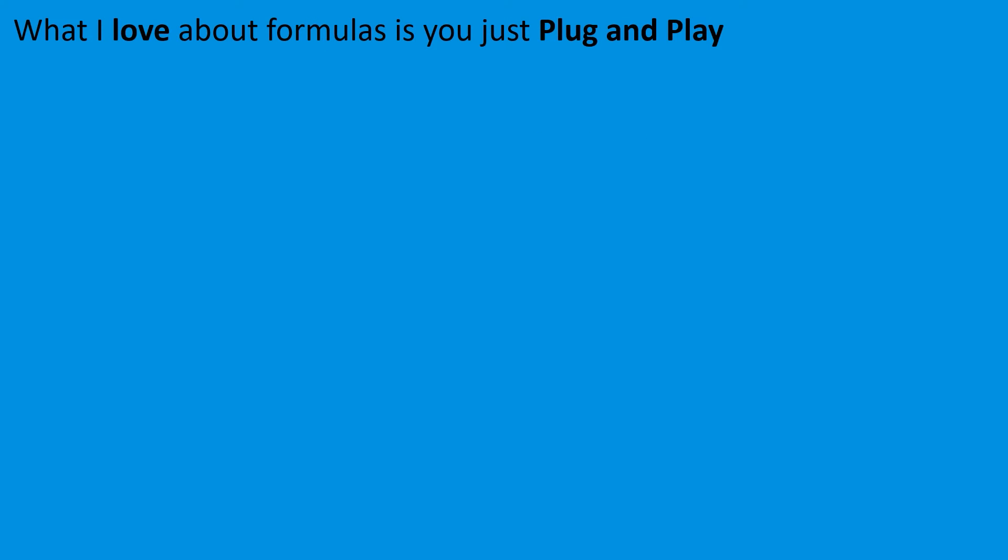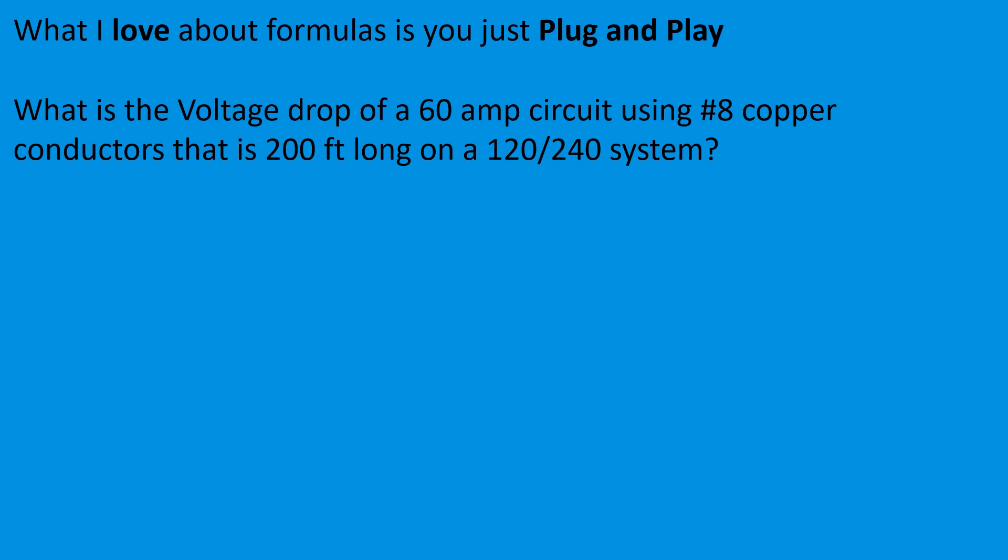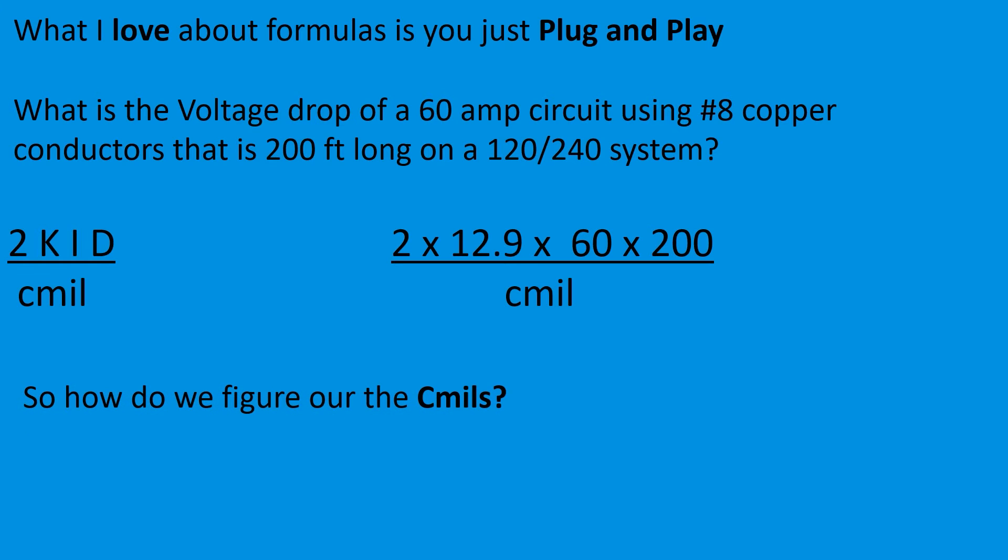What I love about formulas is you just plug and play. What is the voltage drop of a 60 amp circuit using number 8 copper conductors that is 200 feet long on a 120/240 volt system? Okay, so you just take it out. Put 2KID over cmil. So 2 is your constant for single phase. Then your multiplier, we're using copper in this case, so it's 12.9. Then you multiply it by the amperage and then multiply it by the distance. Now we need to figure out what the cmils are, and I'm going to teach you how to do that now.